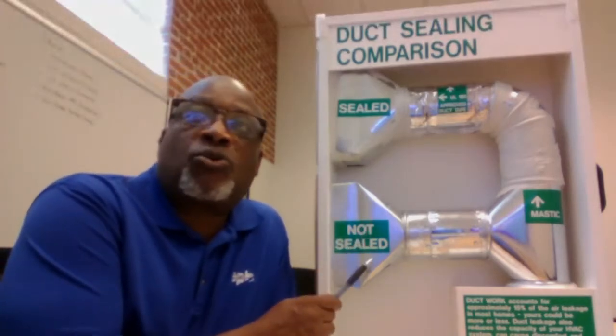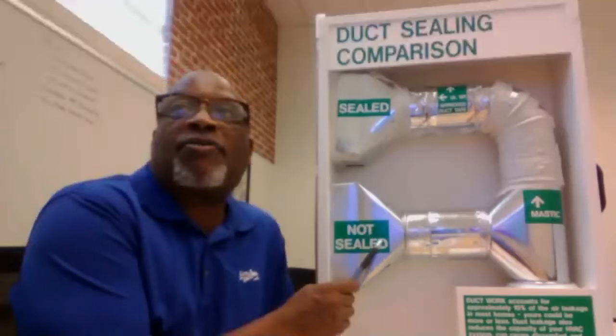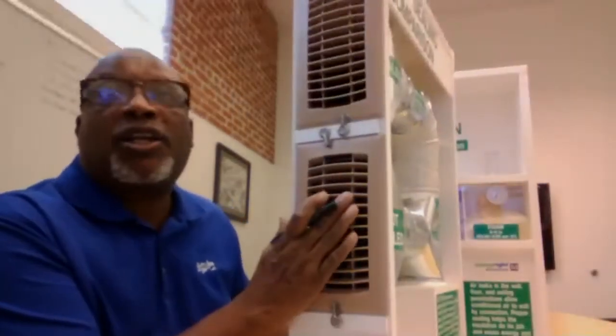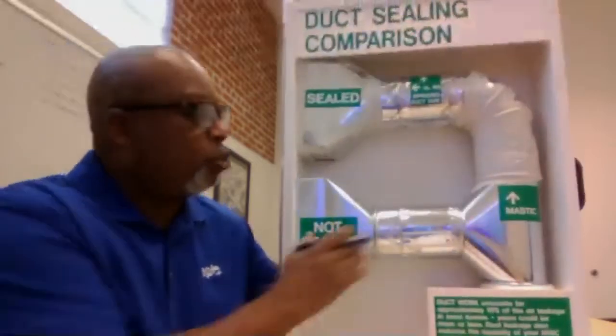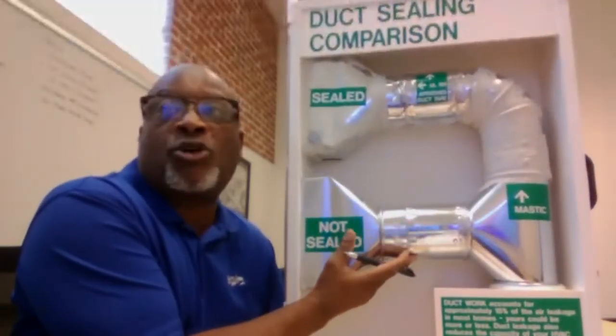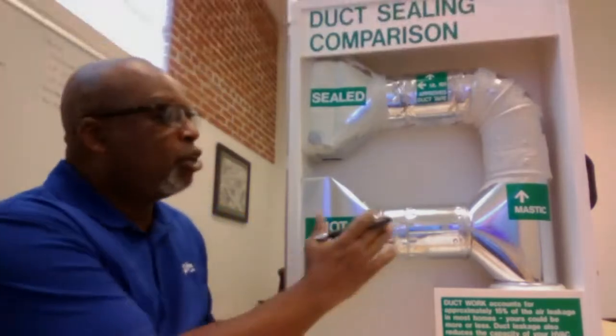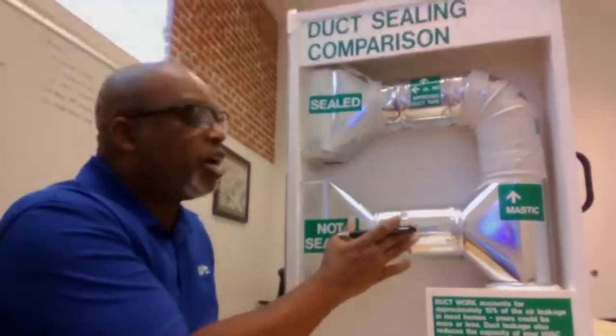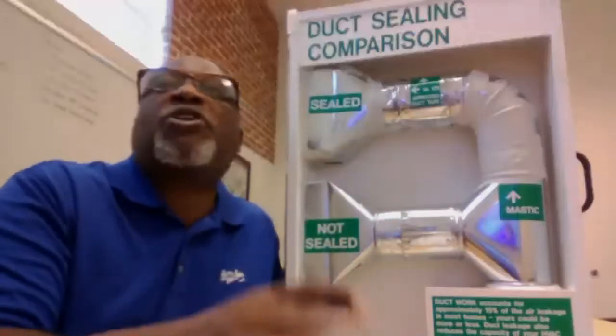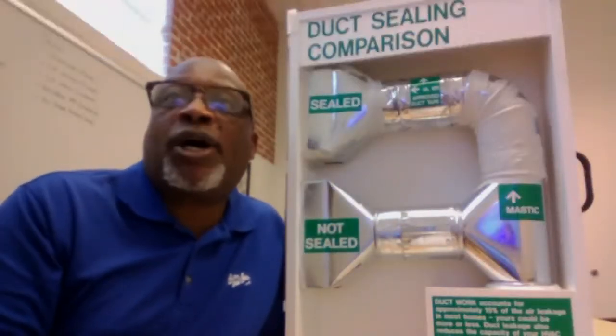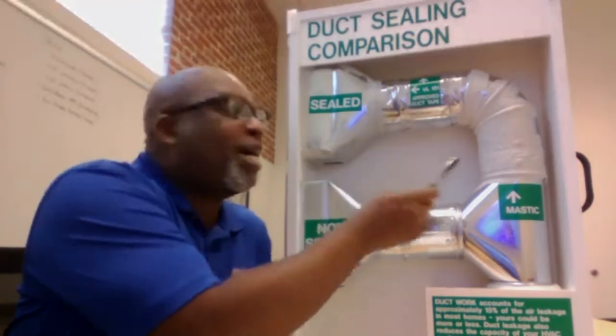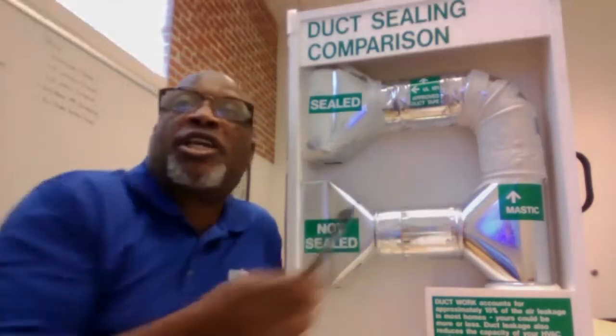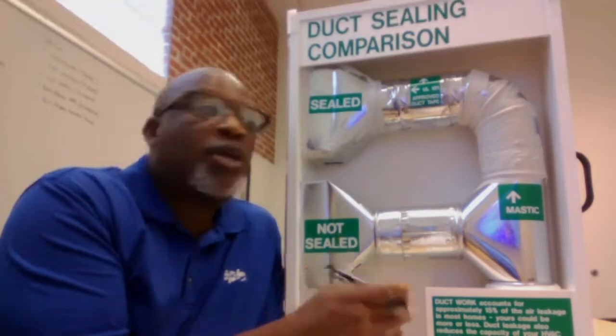Now, number two is your ductwork. In this ductwork, I have right here, if you were here, you could see that on this vent, the ones that don't have mastic on it, or what we call duct butter, lose air all through there. So the air escapes and goes wherever your ducts are running. So the proper way is to put what we call mastic. That's this white stuff you see that you take a paintbrush and paint on, or you can use some mastic tape.